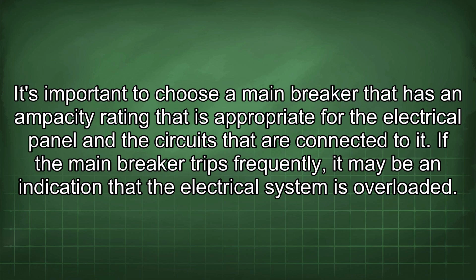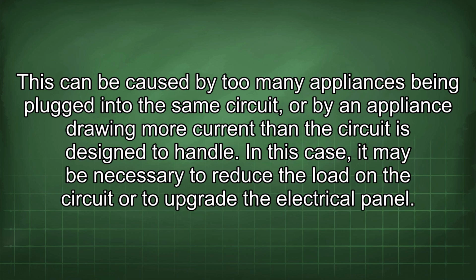If the main breaker trips frequently, it may be an indication that the electrical system is overloaded. This can be caused by too many appliances being plugged into the same circuit, or by an appliance drawing more current than the circuit is designed to handle. In this case, it may be necessary to reduce the load in the circuit or to upgrade the electrical panel.